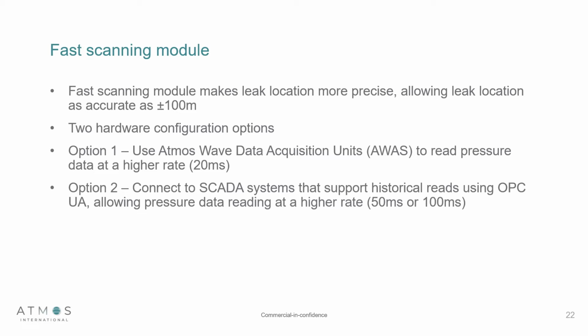So how do we get around improving sensitivity, response time and leak location accuracy? Well, firstly, to improve our flow balance systems, we've integrated what we call our fast scanning module. This fast scanning module makes leak location more precise, allowing leak location as accurate as ±100 meters. This means we can take our flow balance systems that were historically best case scenario ±1 kilometer and dramatically reduce that. So how has Atmos done that? Well, we do that 2 ways. Option 1, we utilize our own data acquisition units. That means Atmos Pipe has gone from being purely a software-based leak detection system to integrating hardware elements to improve its performance. So what we will do is we'll read pressure at a higher data acquisition rate, and if we can, we'll also read the flow data.